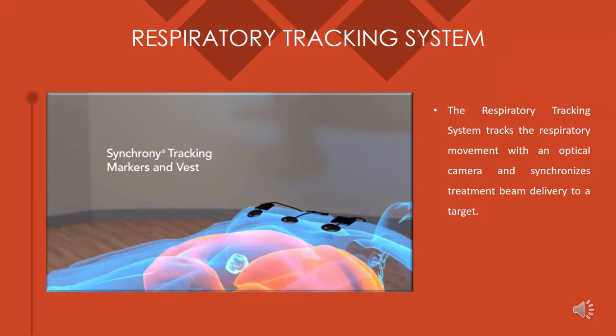The Synchrony respiratory tracking system tracks the respiratory movement with an optical camera and synchronizes treatment beam delivery to the target. This system enables the robot to move with the target and irradiate it during the breathing pattern in real time. This Synchrony system calculates an individual breathing pattern by utilizing 3 cameras and an LED light fixed in a synchrony vest, which the patient wears during the treatment, with the cameras tracking the movement of the chest wall and simultaneously the X-ray imaging system tracking the target.